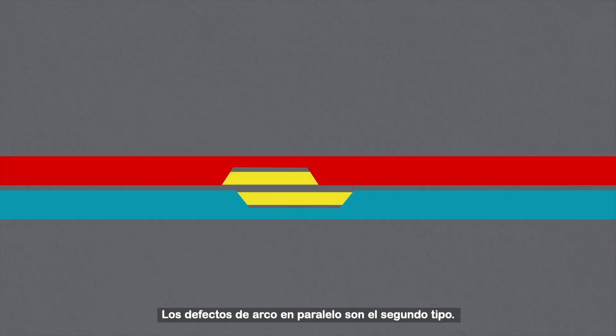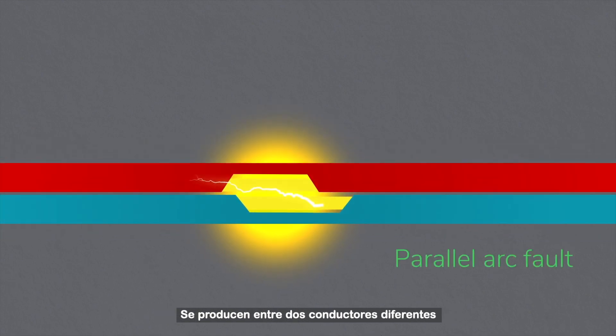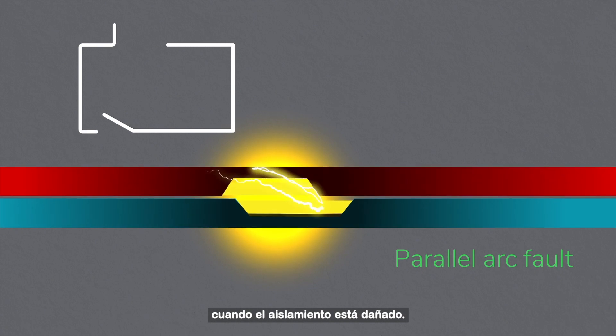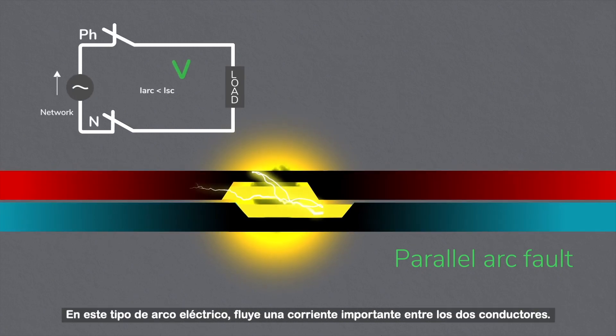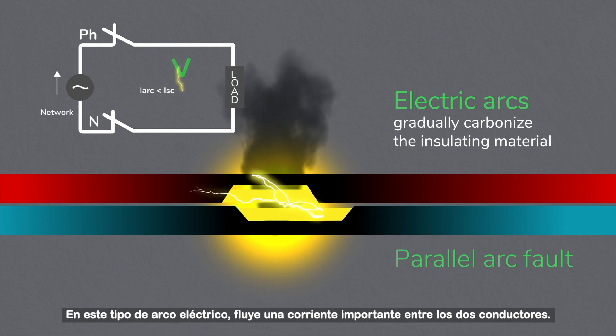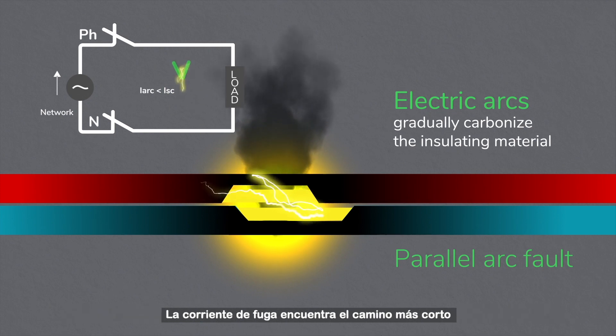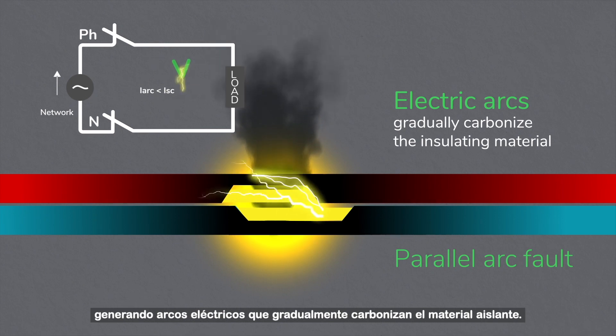Parallel arc faults are the second type. These happen between two different conductors when the insulation is damaged. In this type of electric arc, substantial current flows between the two conductors. The leakage current finds the shortest path by generating electric arcs that gradually carbonize the insulating material.